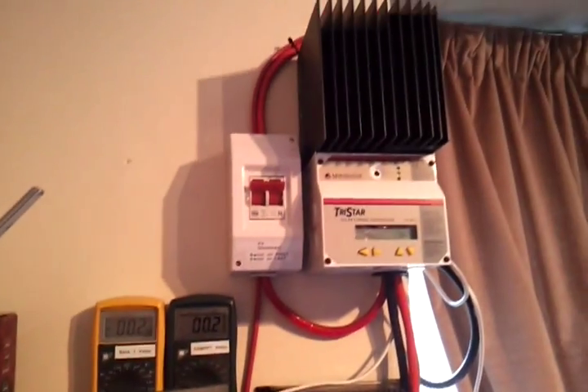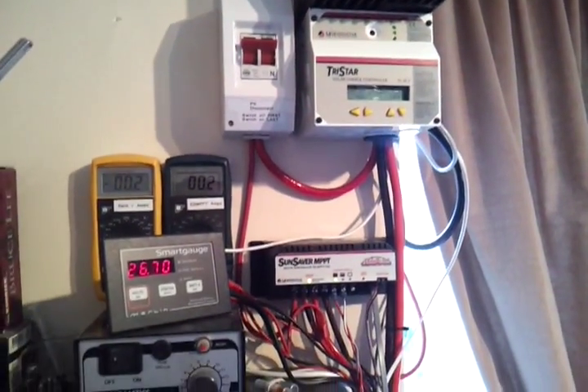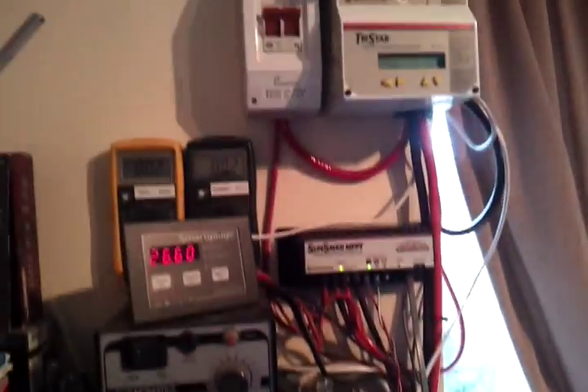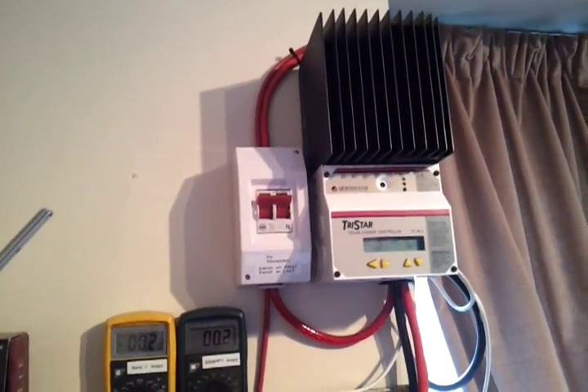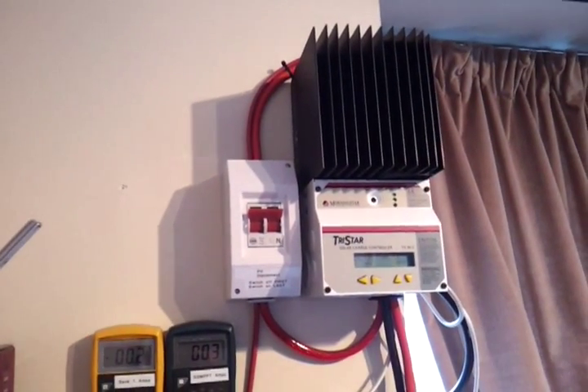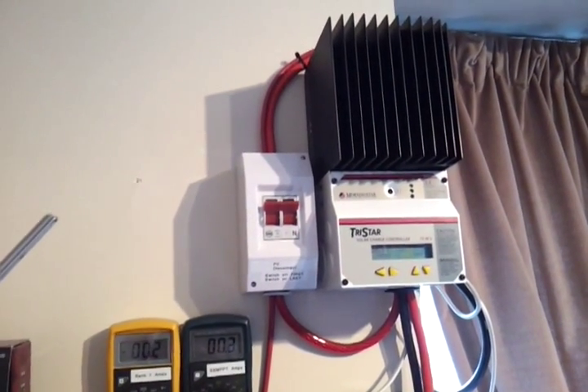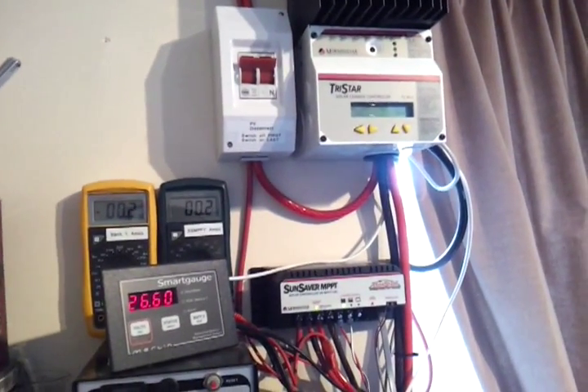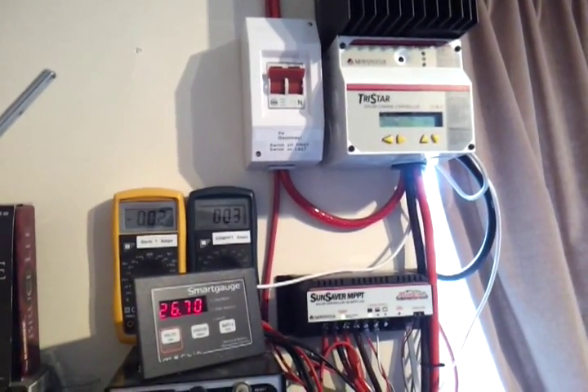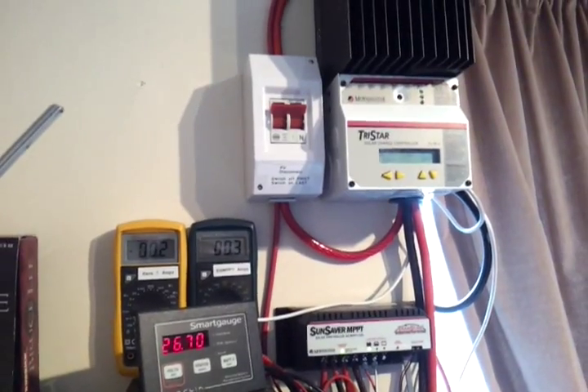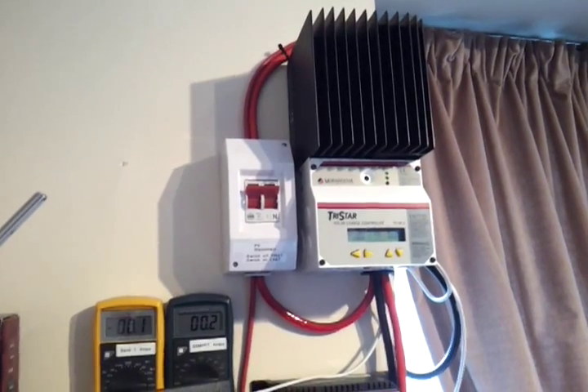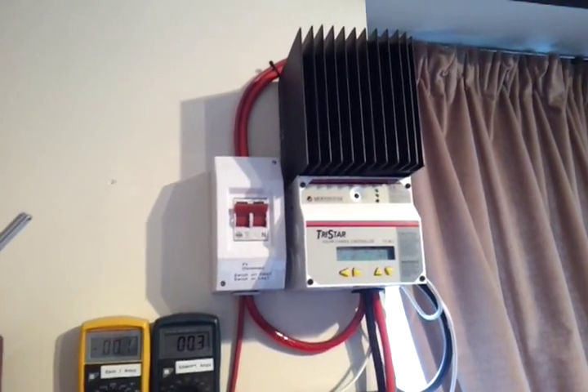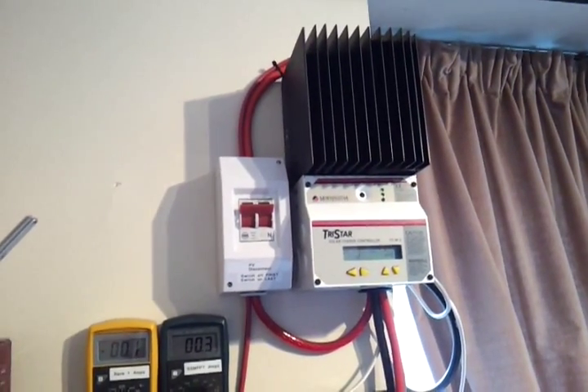Reprogrammed the chargers last night so I am using temperature compensation. The sensors are still plugged in over there, not measuring the battery pack temperature at the moment. I might use that sensor input for something else. I have set the range on the temperature compensation to be from 25 degrees C as the nominal temperature for compensation adjustment. So lower than 25 degrees C it makes no adjustment, which is important. But above 25 degrees C it would start to reduce the charging voltage.